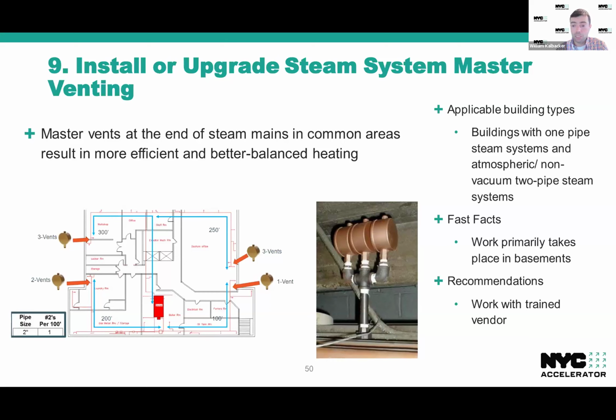This work is primarily going to take place in the basements. That's where the biggest steam pipes are in the building that fill up with the most air that need the most venting. And it's really recommended to work with a trained vendor who's done this before, so that you can ensure that it's done properly.